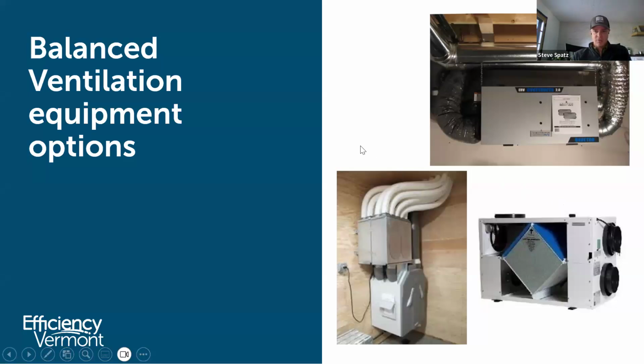So another critical piece of this, as I was saying a moment ago, when it comes to the duct design, you really want a ventilation system to be operating in the background, so that the occupants are not even aware that it's there doing what it's doing. Meaning that you want a piece of equipment and a system that is operating quietly so that they don't hear it, and that also you're getting good and effective sensible heat recovery, so that you're not moving cold air into the rooms and onto the occupants.